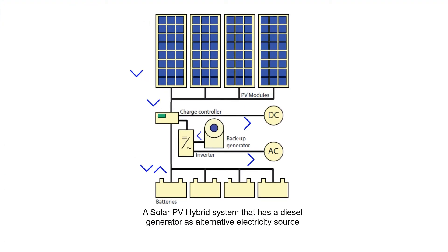A schematic of a hybrid system has been shown here. In order to optimize the different methods of electricity generation, hybrid systems typically require more sophisticated controls than standalone or grid-connected PV systems. In this case of a PV-coupled diesel system, the diesel engine must be started when the battery reaches a given discharge level, and stopped again when the battery reaches an adequate state of charge. The backup generator can be used to recharge batteries only, or to supply the load as well.